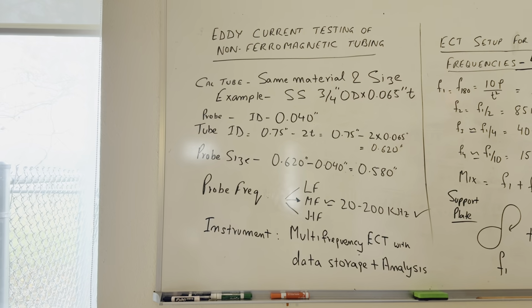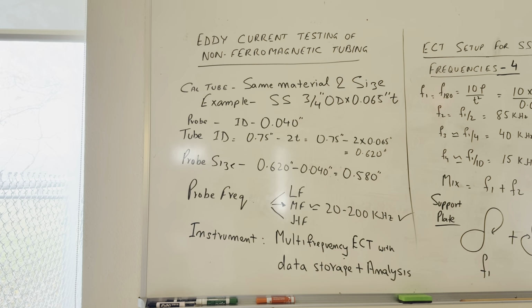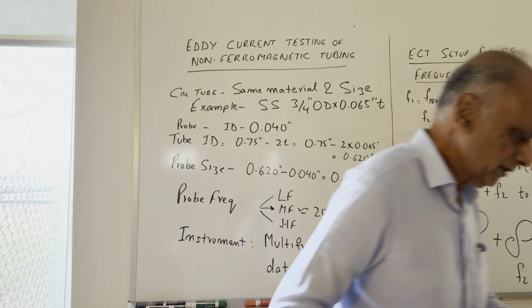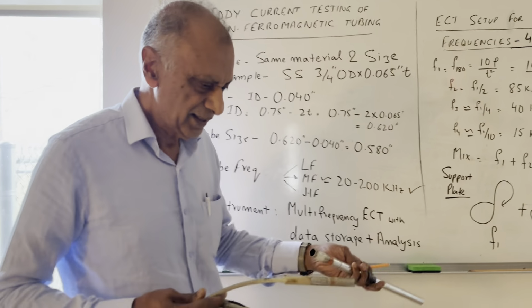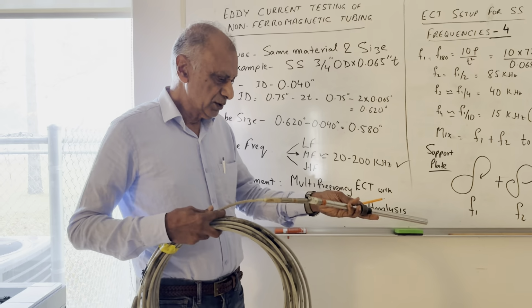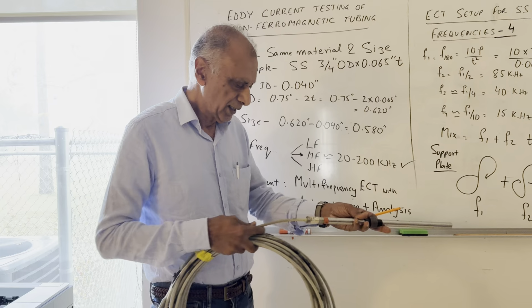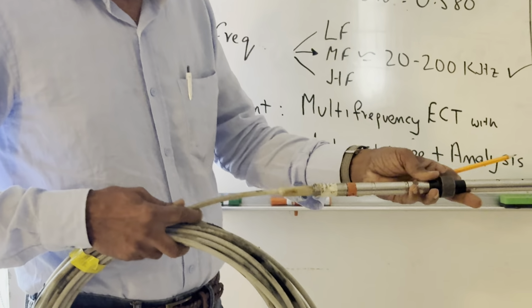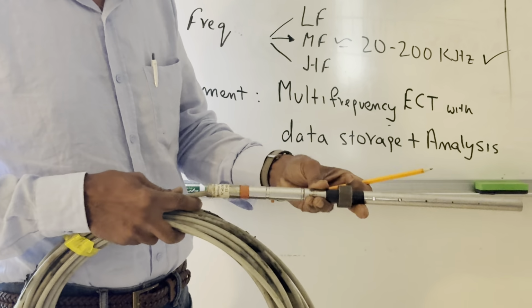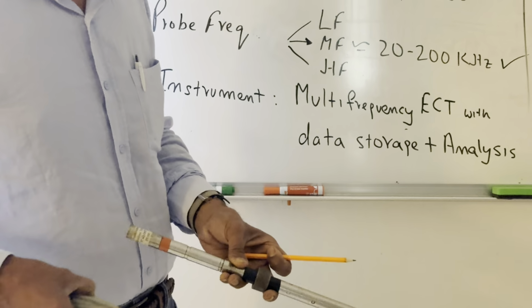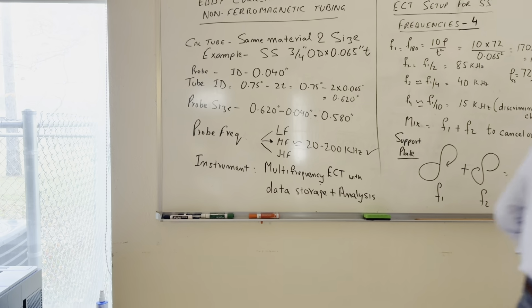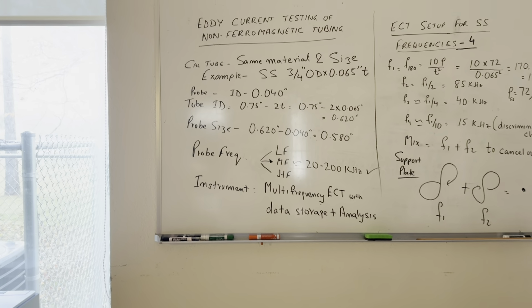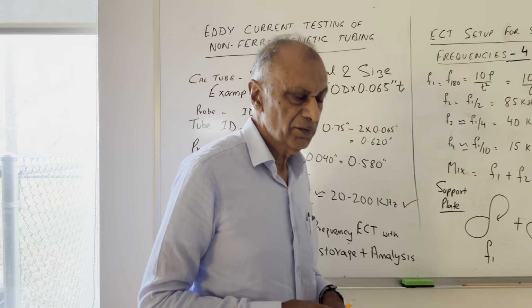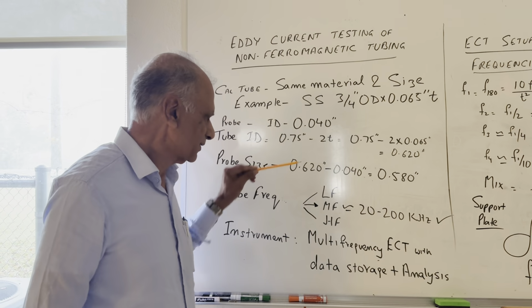And the bobbin probe, here it is. And this is a 580 probe. The size of this probe is 580. And this probe goes right into the calibration tube, and there is some clearance of 40 mils, which is good enough to do the inspection. So remember, when we select this probe, we don't go by the fill factor and all that stuff. We go by this 40 mil clearance.